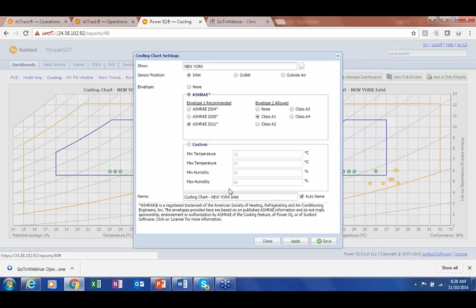Our dashboard is highly user configurable, where with one click you can adjust what ASHRAE range you're leveraging, 2004 or 2011, what allowable ranges you want, whether you want to focus on inlet temperature or cold aisle, outlet or hot aisle, or outside air, or define your own envelope based on your own parameters.